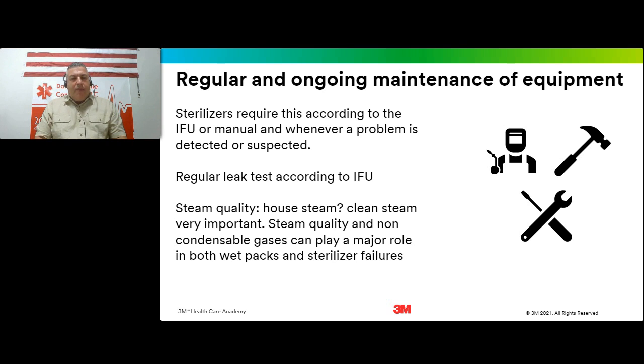That steam, you know, essentially was intended to heat, sometimes cool the building. But then we drill a hole into the pipe and pull it into the sterilizer. Some of us are lucky enough to take that steam and do a clean steam system. We could use the house steam to boil more purified water to make clean steam. Some people may even have their own dedicated boilers, but I don't really see that too often out there, rather than a steam-to-steam system.